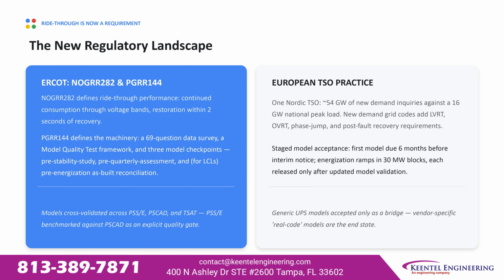European TSO practice tells a similar story. One Nordic TSO reports roughly 54 gigawatts of new demand inquiries against a 16 gigawatt national peak load. New demand grid codes there add low voltage and over voltage ride-through, phase jump response, and post-fault recovery requirements. Model acceptance is staged. The first model is due 6 months before interim notice, and energization ramps in 30 megawatt blocks, each released only after updated model validation. Generic UPS models are accepted only as a bridge. Vendor-specific real code models are the end state.